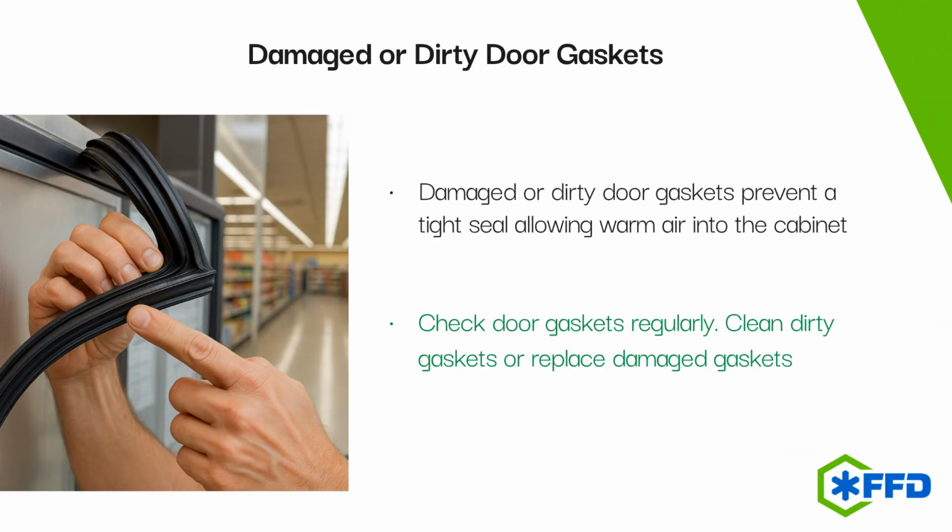Damaged or dirty door gaskets will prevent a tight seal on doors allowing warm air into the cabinet. Check gaskets regularly for signs of dirt or damage. Clean dirty gaskets or replace damaged gaskets to re-establish a sufficient seal on closed doors.